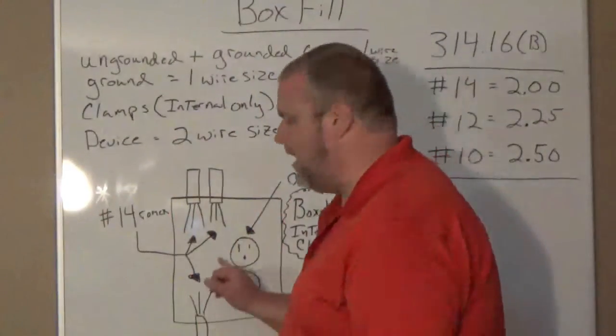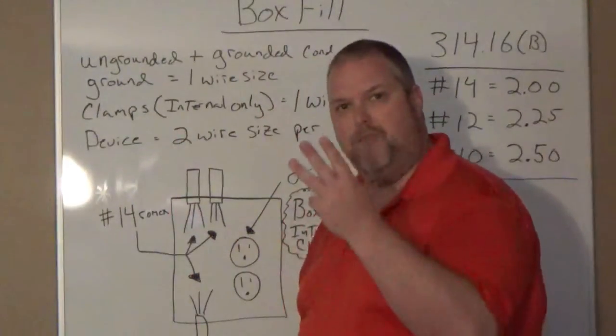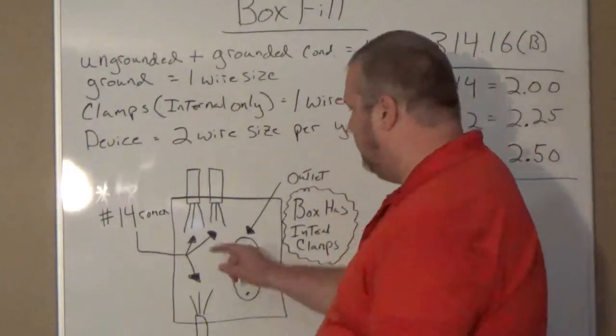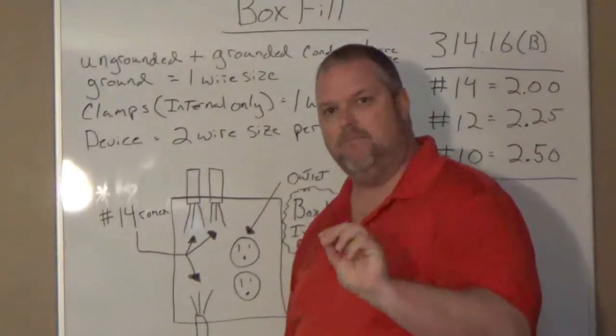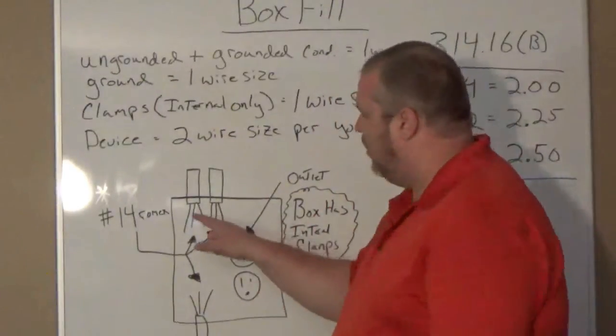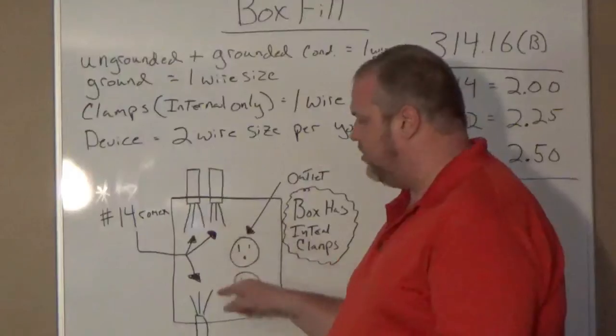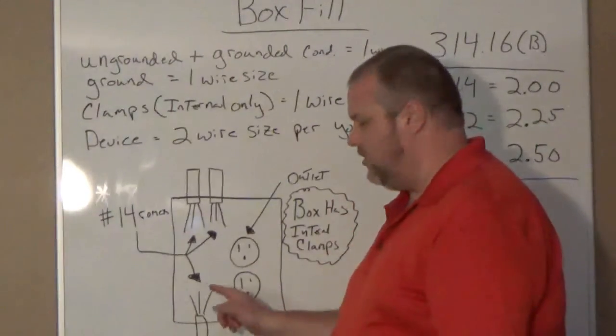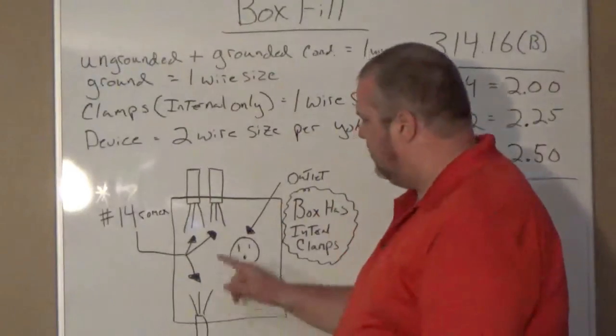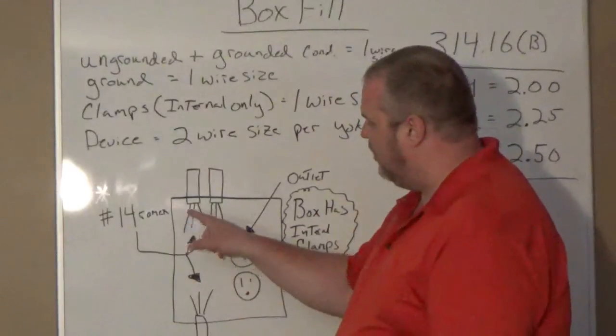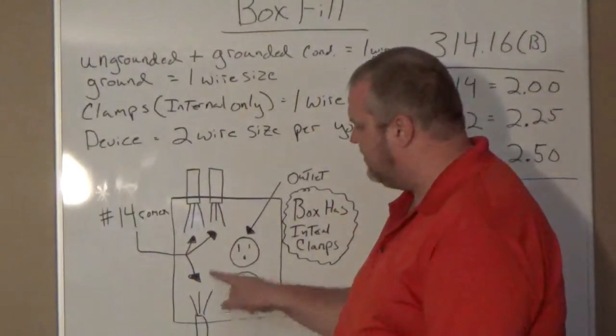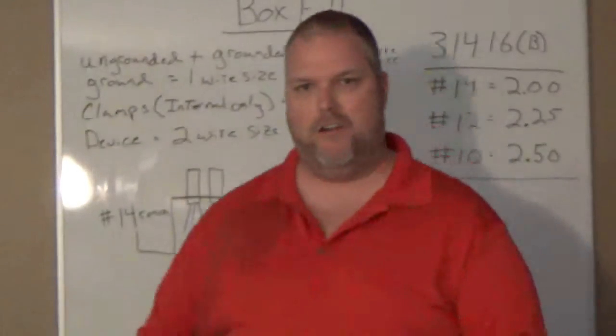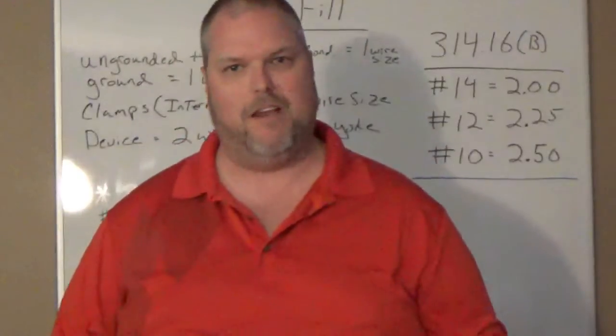Let's count the grounds. We have three grounds, but we're only counting them as one number 14. So now we have seven. The internal clamps are counted as one. The ground is counted as one. So that's going to bring us, we have one, two, three, four, five, six, the ground being seven, the internal clamps being eight.